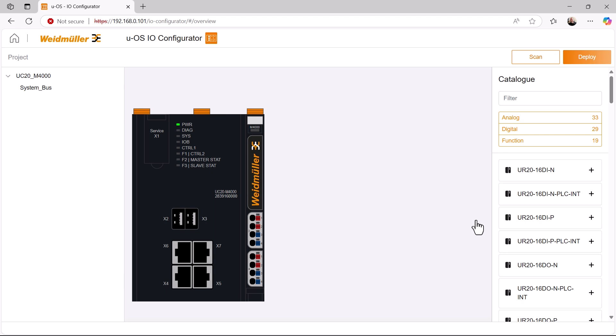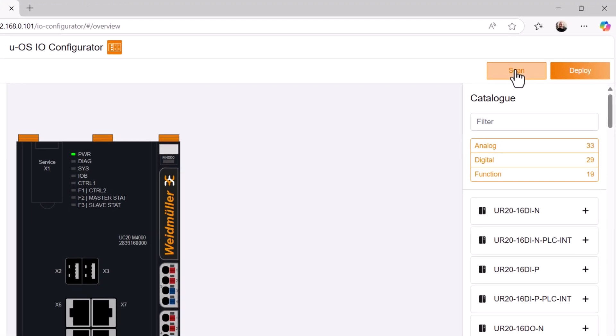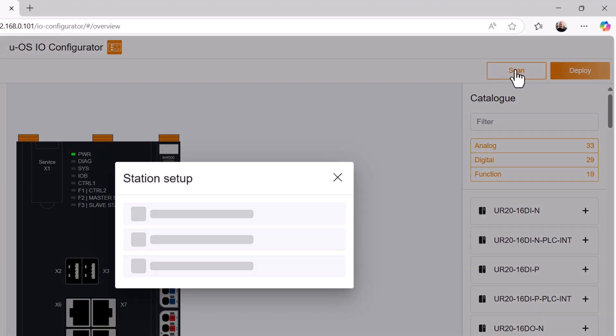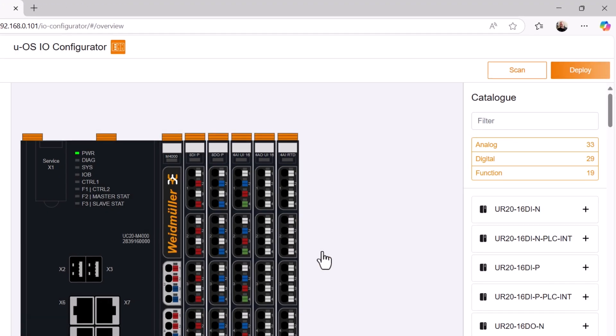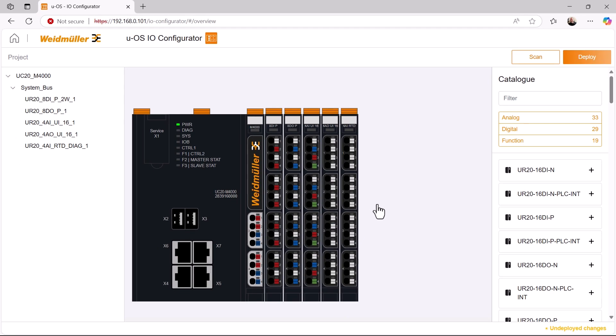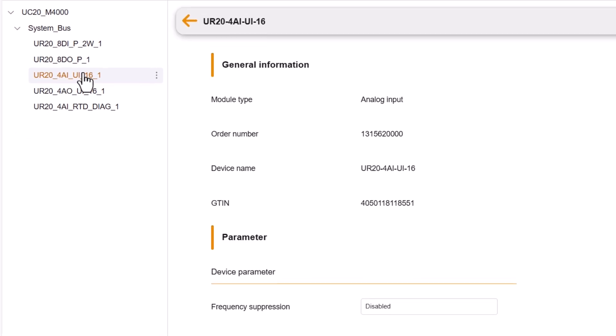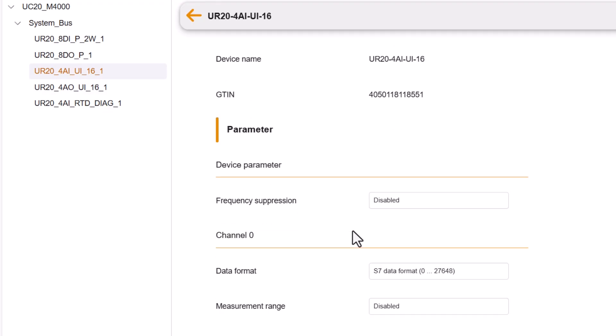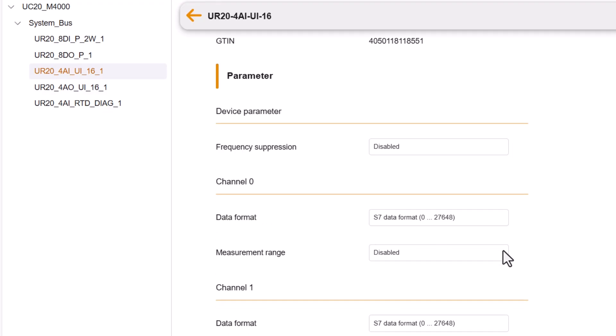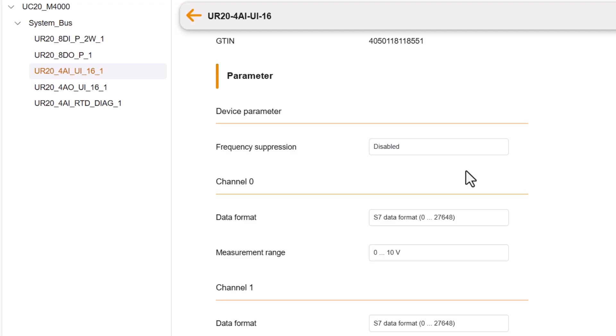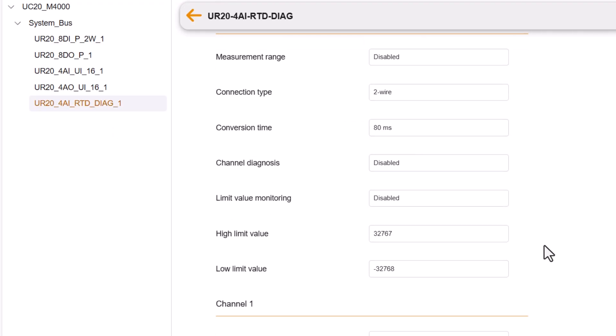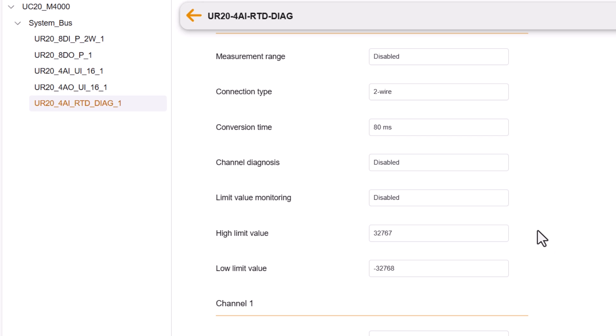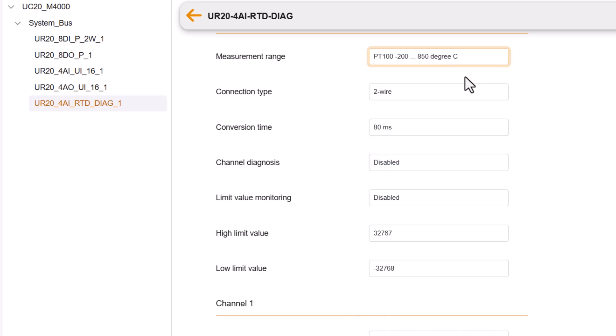In the UOS IO configurator, we first configured the u-remote modules connected to the U-Control system bus. To do this, we used the scan button to have the system automatically detect the connected modules and then configured the channels for the analog inputs used. Firstly, the analog input with the connected potentiometer for the temperature limit value. Here we used a measurement range from 0 to 10 volts. And on channel 0 of the temperature measurement module, we specified that we have connected a PT100 with a measurement range of minus 200 to 850 degrees Celsius.